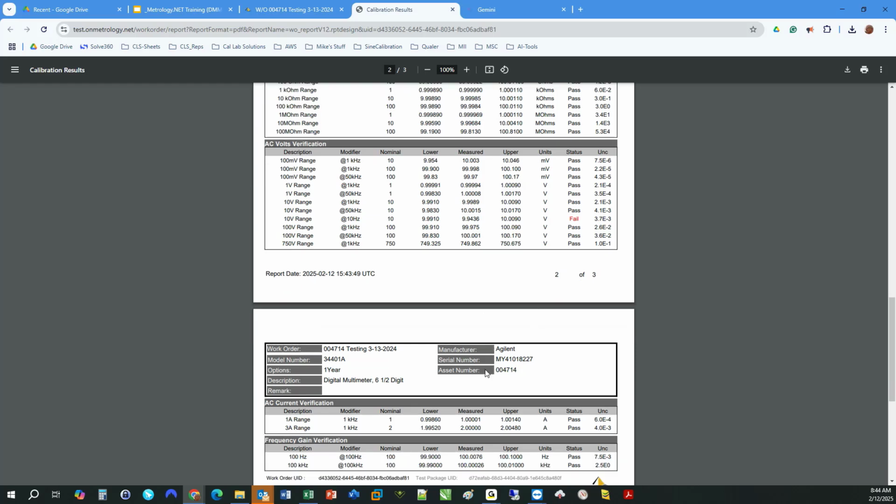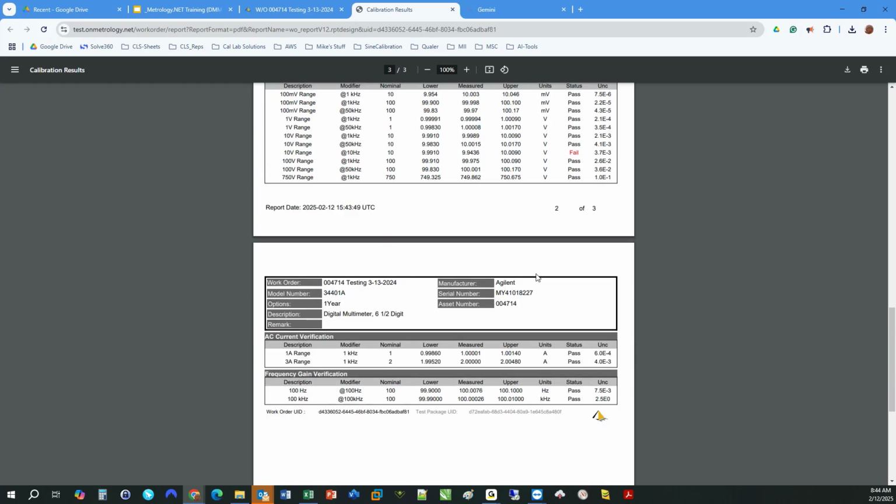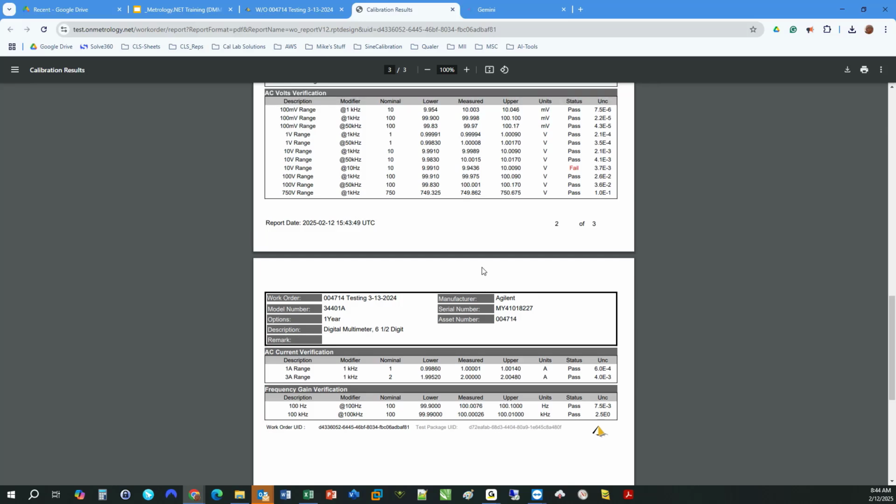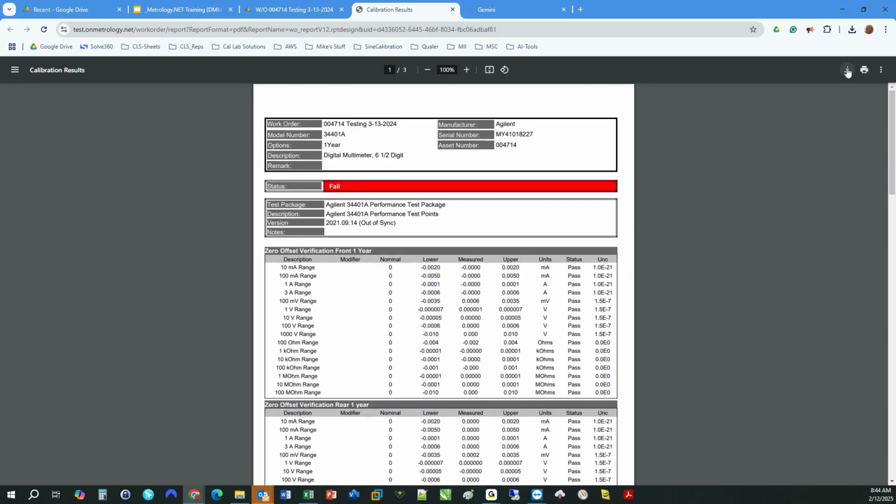We can build cal reports that'll say something's not tested; we just haven't built that yet for any of the customers out there. And then the users can download this and attach it, or there's a whole bunch of things that they can do with the REST API, pulling back all the calibration data if they want the raw results.